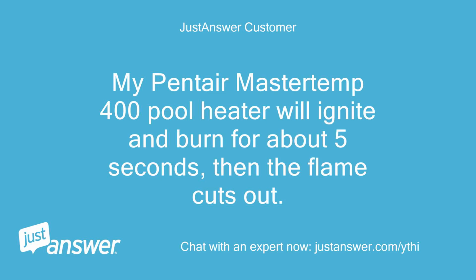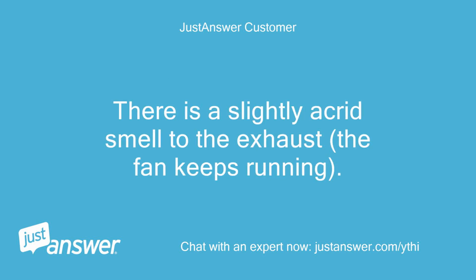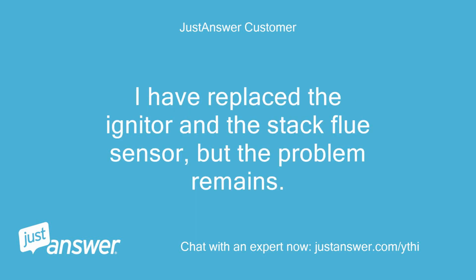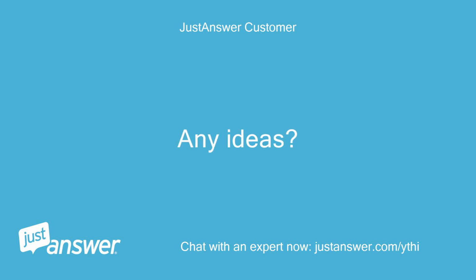My Pentair Mastertemp 400 pool heater will ignite and burn for about 5 seconds, then the flame cuts out. There is a slightly acrid smell to the exhaust, the fan keeps running. I have replaced the igniter and the stack flue sensor, but the problem remains. Any ideas?